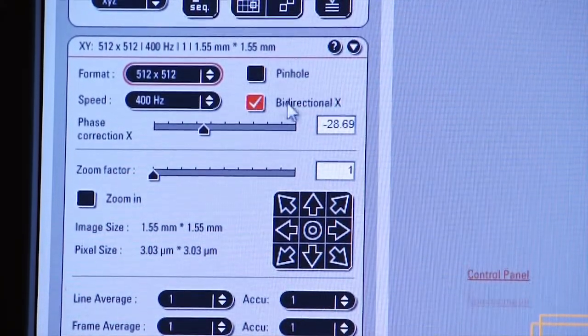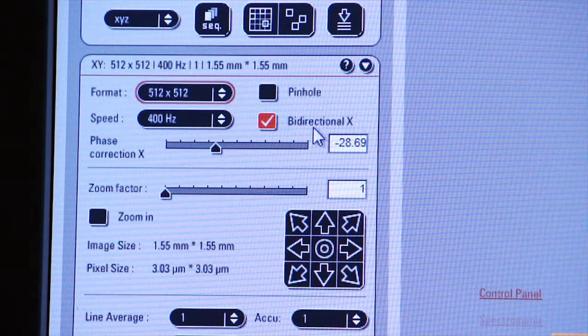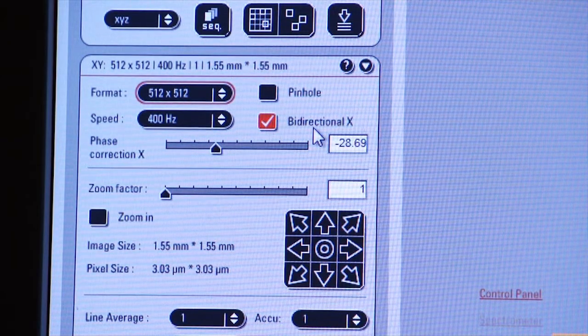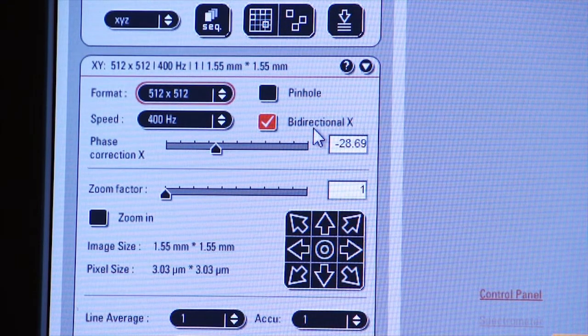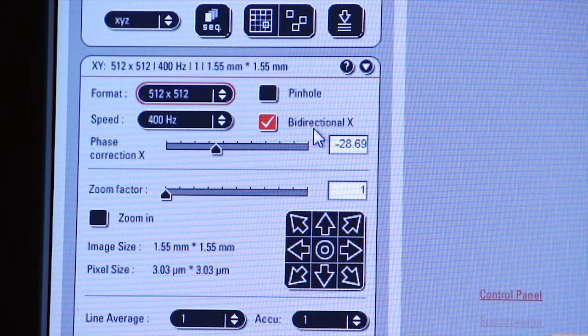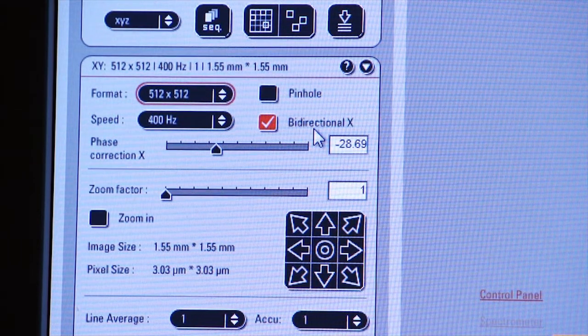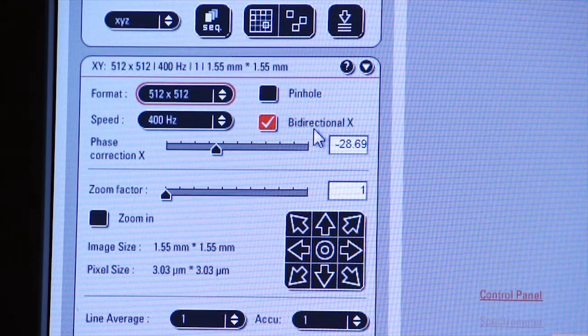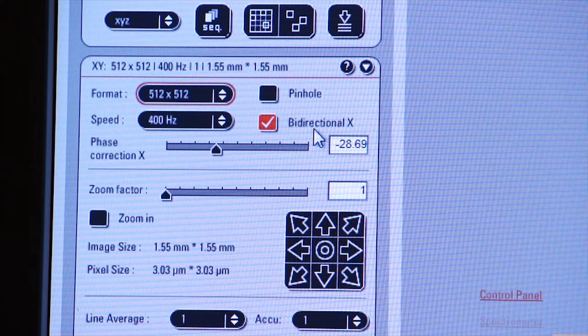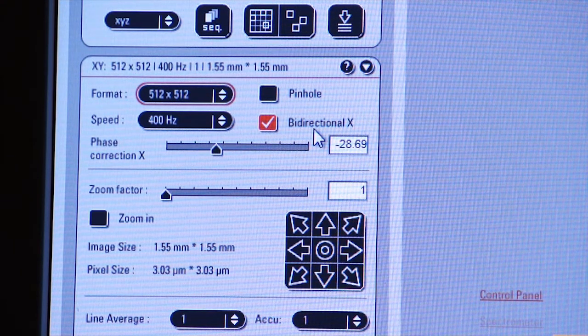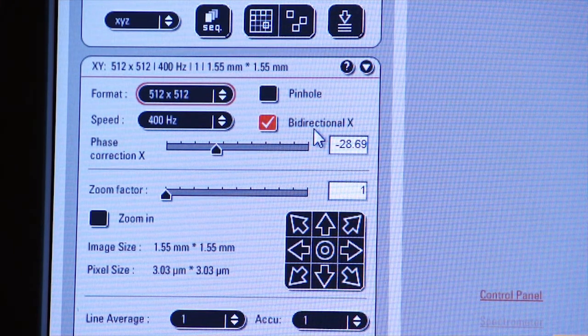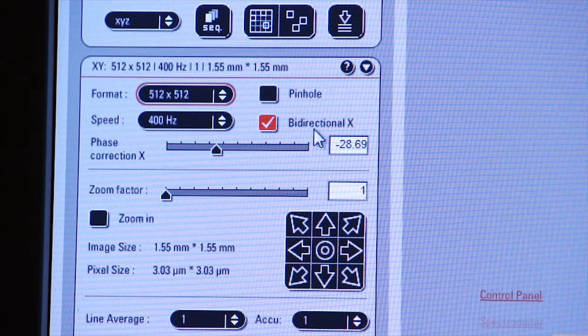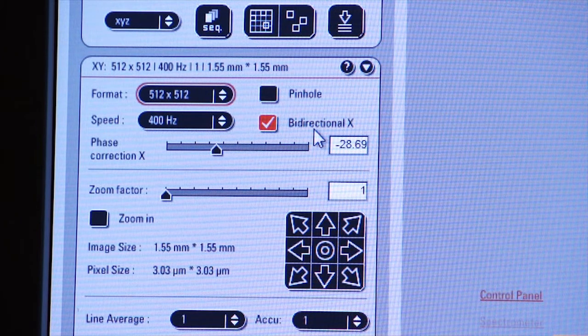The system, when it scans an image, scans in X, and then it drops down and scans in X again. It drops down in Y and scans in X again. Normally, it scans from left to right in X. It goes back to the beginning of the next line of pixels, scans across those pixels, goes back to the next line, and so forth. You can change it to bi-directional, so that the system will scan and align in X, drop down, and scan backwards, and so you can increase your speed by using bi-directional scanning.